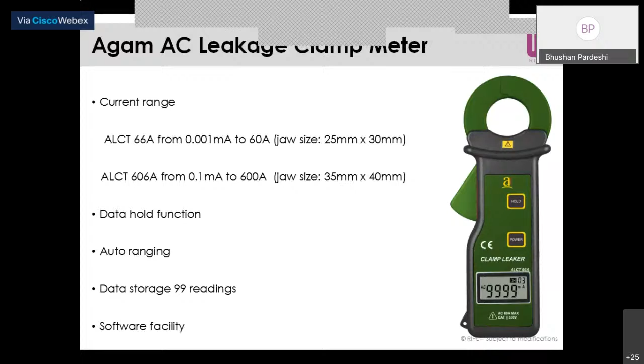Yes, okay. Now, another thing is the AC leakage clamp meter. Leakage is one of the important things when it comes to delta connections or star connections. So leakage current is one of the important points one needs to identify and rectify. This leakage clamp meter allows one to measure the leakage current available in the system. As we all know, more than 10 milliampere of current is harmful for a human body, and if it crosses a limit of 25 milliampere, it can lead to the death of a person. So it is very important to measure the leakage of any system.